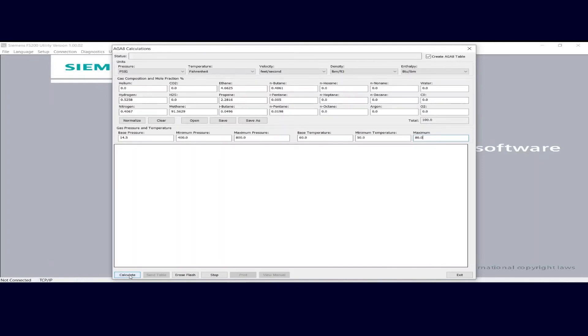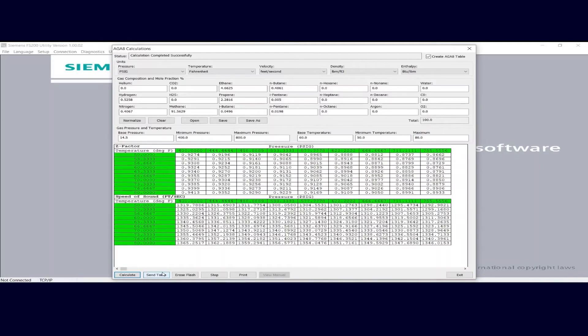Come down to the bottom and click the Calculate button. The FS-200 tool will now compute an AGA-8 table that you can upload to your flow meter. What you see is a compressibility factor matrix: the top section shows temperature on the y-axis over your application range — 50 to 80 degrees in this case — and pressure over the range you entered from 400 up to 800 psi. For each intersection of temperature versus pressure, you'll see a compressibility factor based upon your gas mole fractions. The lower section is a sonic velocity matrix, so based upon pressure and temperature you can find the sonic velocity expected under those conditions.